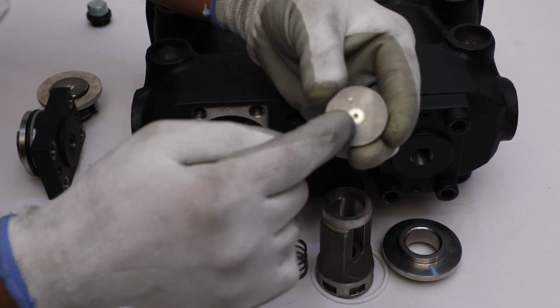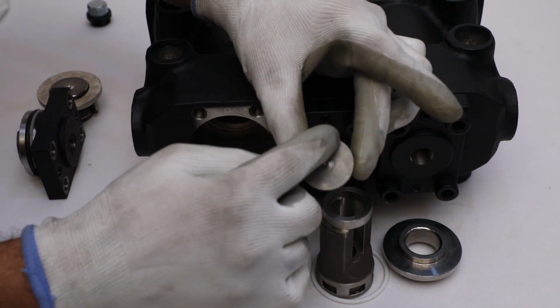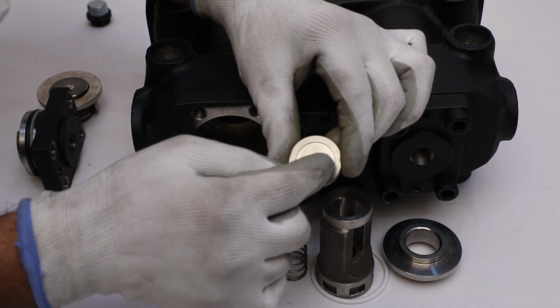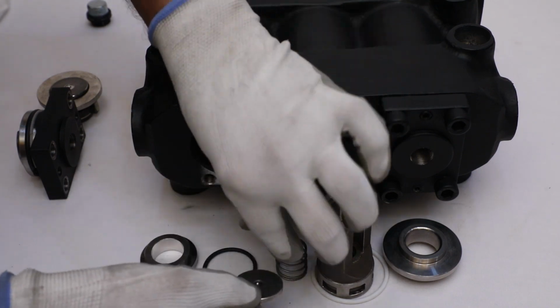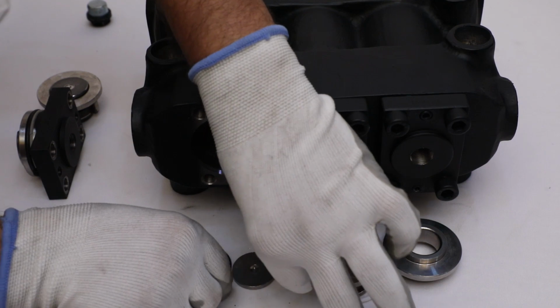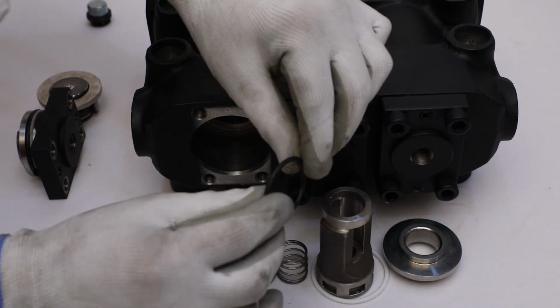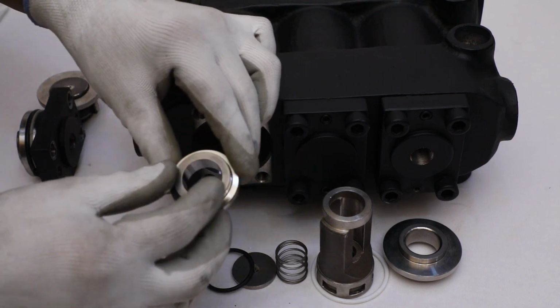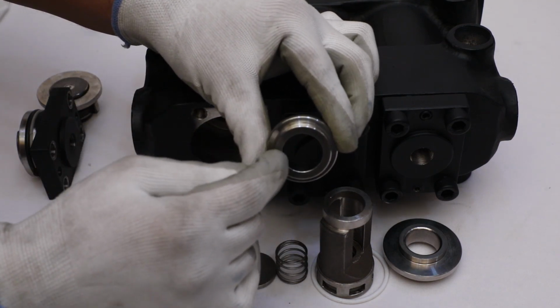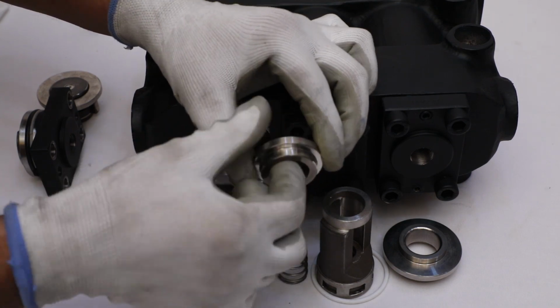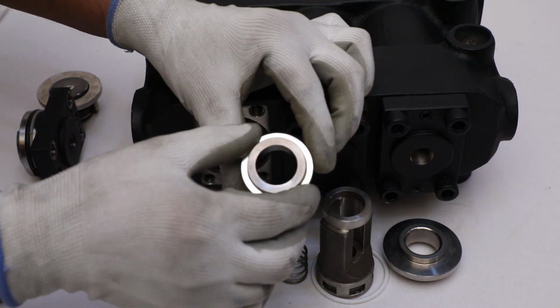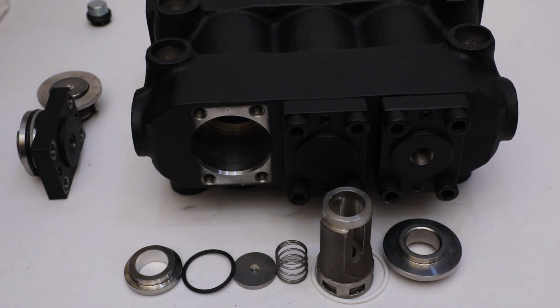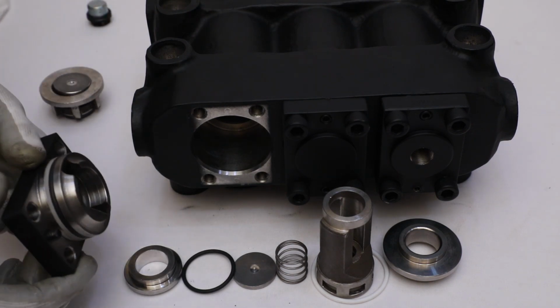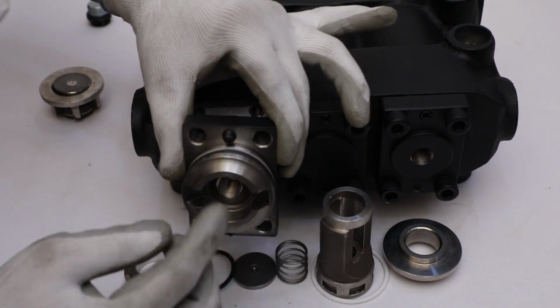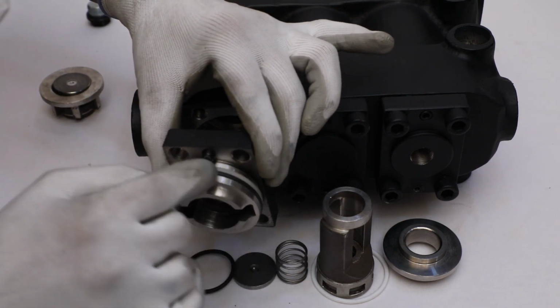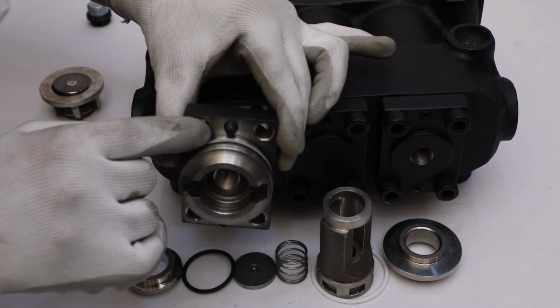Inspect both sides of the surface of suction and discharge valve plate for any wear and dent marks. Check O-ring for any damage. Look into the inner and flat surface of suction valve seat for any wear or damage. After that, check the inner, outer and groove surface for the valve holder for any type of damage.